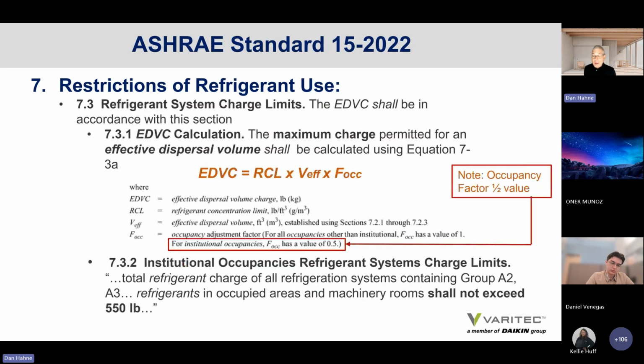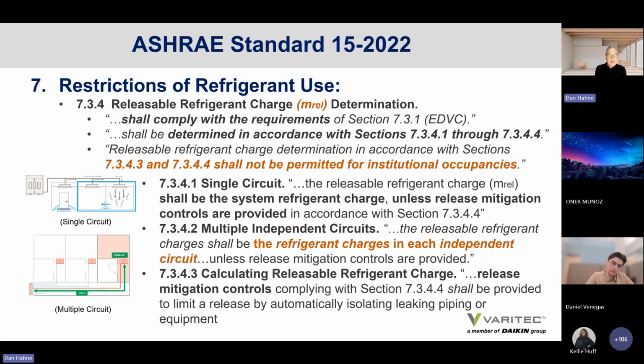Oh, and there's one other rather interesting note under 7.3.2: the maximum total refrigerant charge of all refrigerant systems containing group A2 or A3 refrigerants in occupied areas and machine rooms shall not exceed 550 pounds. So just be aware of that limit, and this information is embedded in the standard under these section references.